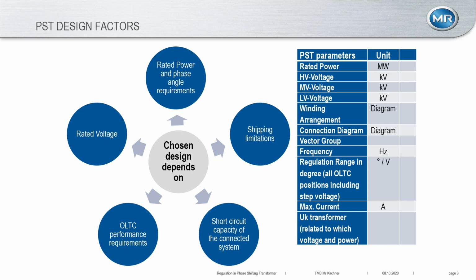And in many cases, phase-shifting transformers are very huge pieces of equipment, and they have to be shipped around the world. And the shipping limitations, especially if you leave the waterway and go on railway or on the road, can cause certain problems. So this is something that has to be considered, of course. And the OLTC performance requirements are a point for phase-shifting transformers. In many cases for OEMs that are new in this business, this is kind of a new situation because when you create a normal transformer, you would come up with a design, you select an OLTC and everything is fine and you go with it.